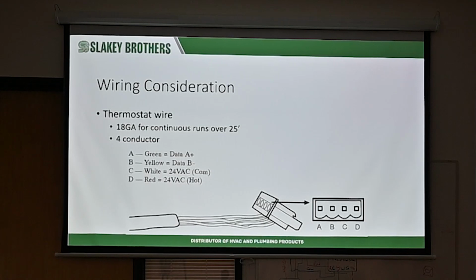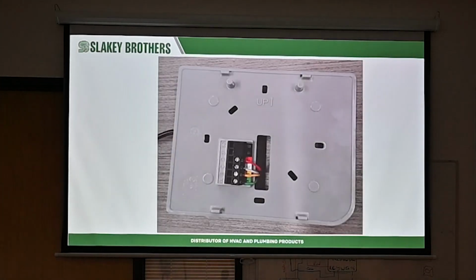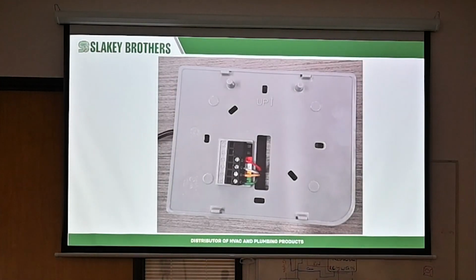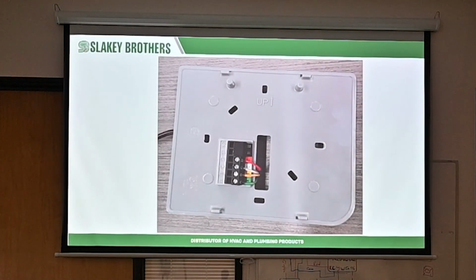Our wires, 4 conductors, the traditional A, B, C, D. C and D is your 24 volts, A and B is your communication line. 18 gauge is fine, 4 conductors. Man, you can go a long distance with 18 gauge, which is fine. You'll see if you have to go a little bit further, you sometimes have to put a resistor, but the odds of going over that distance, we'll see here in a second, are pretty rare. Connect it onto your Connex, make sure it's nice, clean connections.